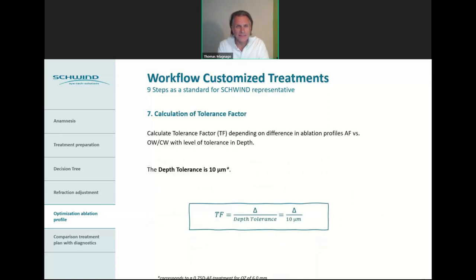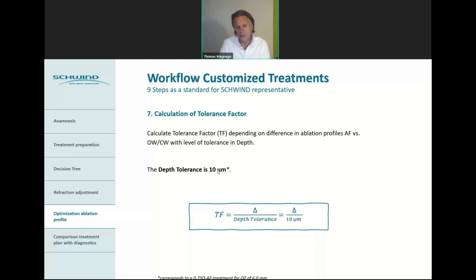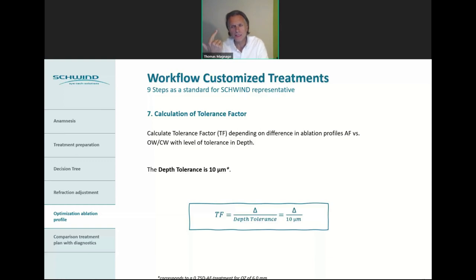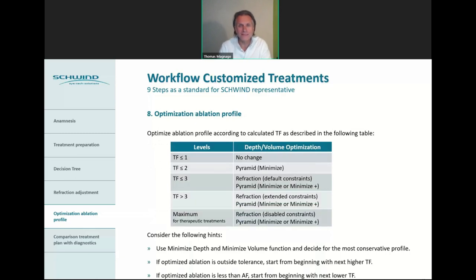Step 7 is the calculation of the tolerance factor. This tolerance factor depends on the difference in ablation profile between aberration-free and customized treatments, with a level of tolerance of 10 microns — because this represents about three-quarters of a diopter in an aberration-free treatment at a 6 mm zone. In our example, the delta was 15 microns: 15 divided by 10 microns gives a tolerance factor of 1.5. This 1.5 tolerance factor guides us for the next step — the optimization of the ablation profile.